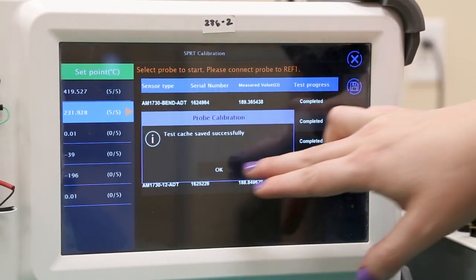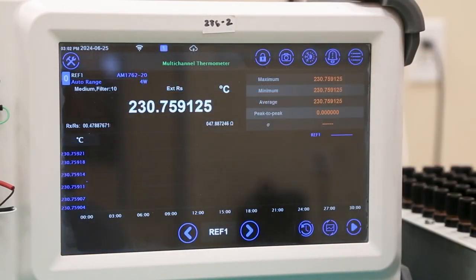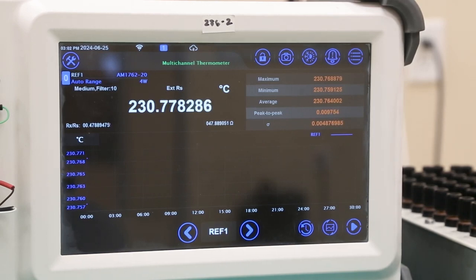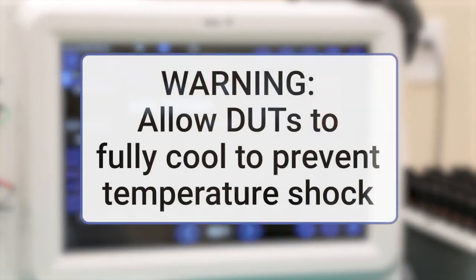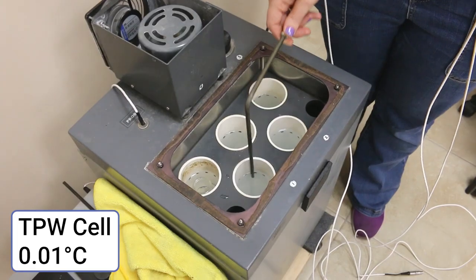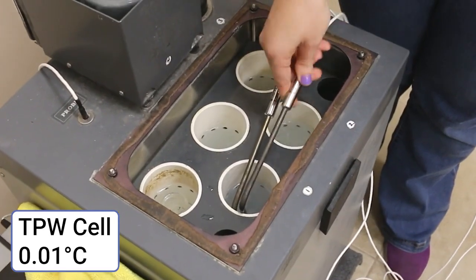Once finished with all 5 probes, the temperature of each cell should be taken once more with the check standard. Since the next calibration point is the triple point of water, with a much lower temperature than the tin freezing point, it's important to allow the probes to fully cool before beginning measurements. Once they have reached room temperature, we will add all 5 probes to a pre-cooling area in the bath.